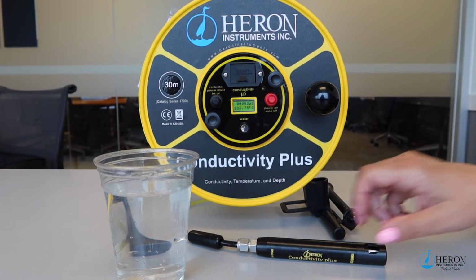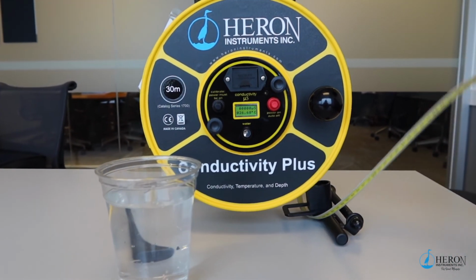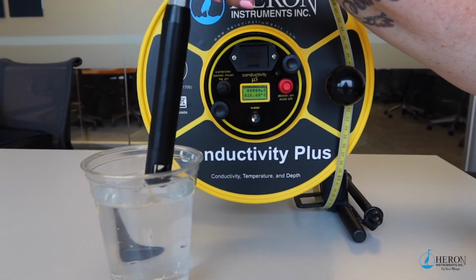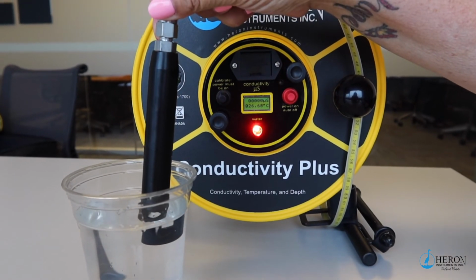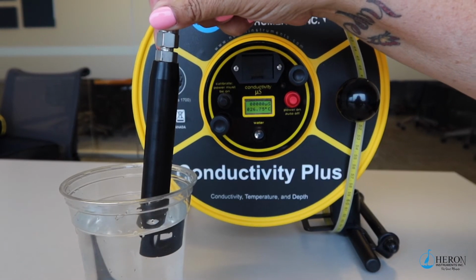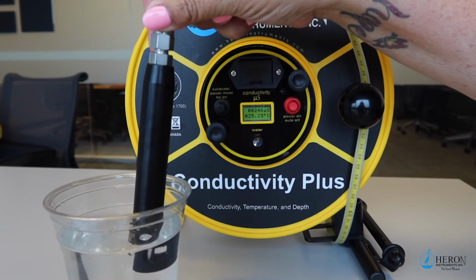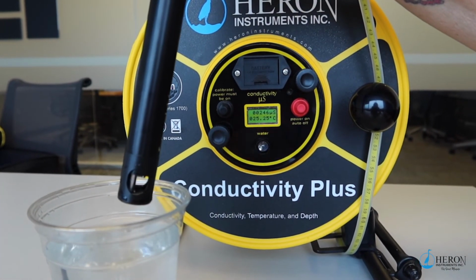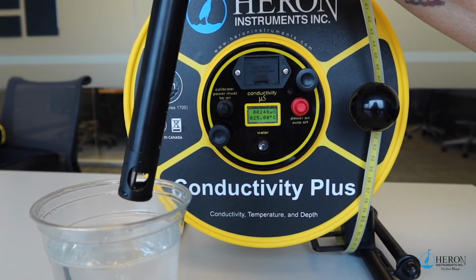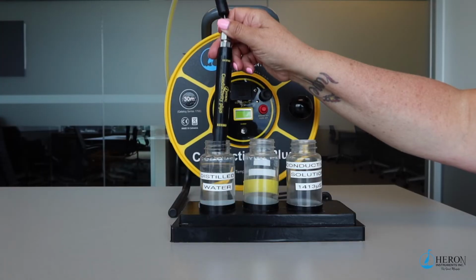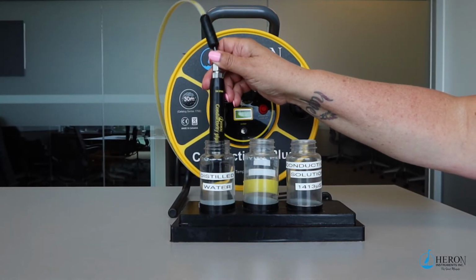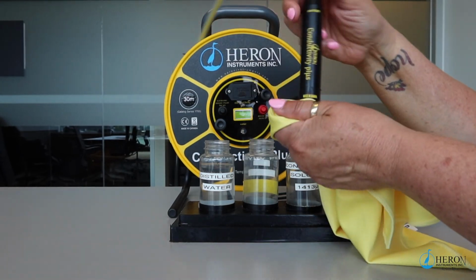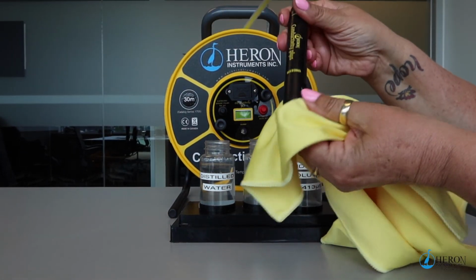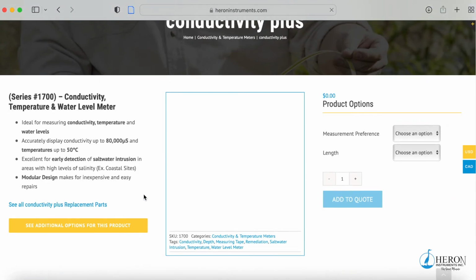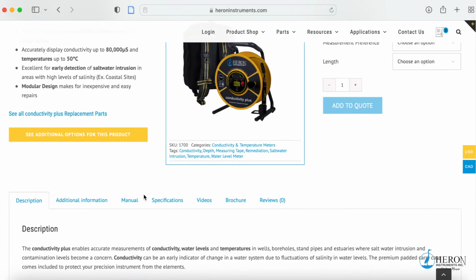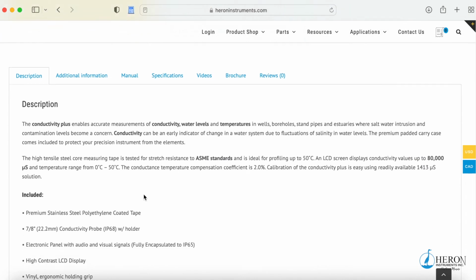Place the probe in tap water. The unit will emit a short audio and a visual indication, and the display will update with temperature and conductivity readings. Remove the probe from the water. The unit will emit an intermittent 3-second audio and visual indication. Before each measurement session, meaning a full day in the field, you should calibrate the Conductivity Plus. The full video on how to calibrate your conductivity meter can be found on our website.